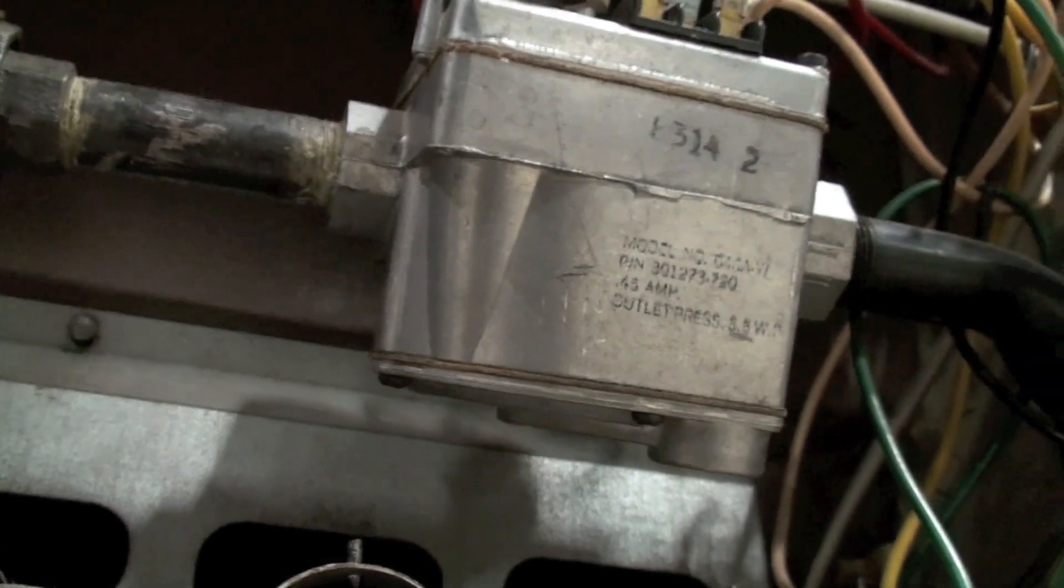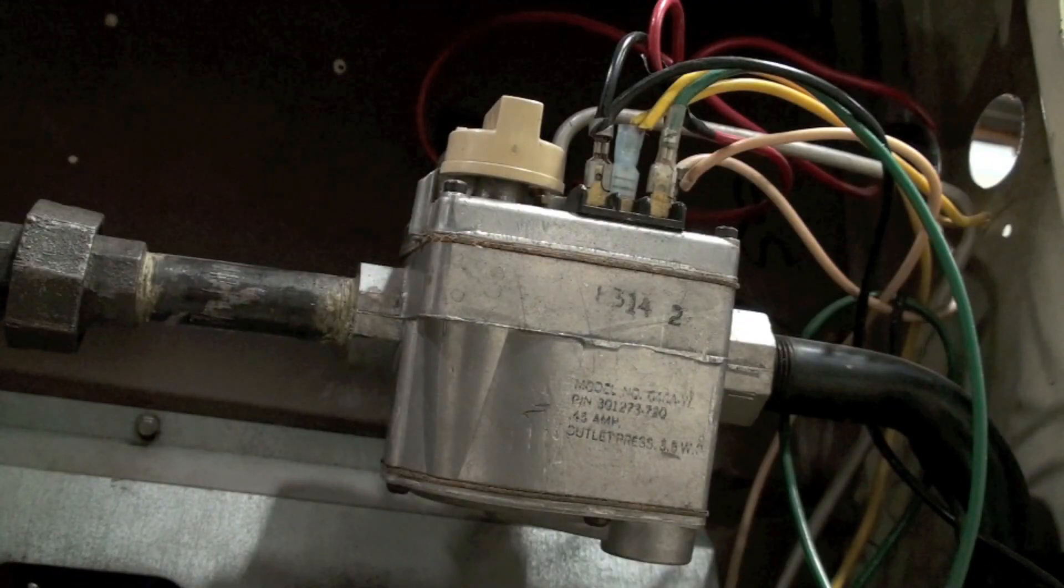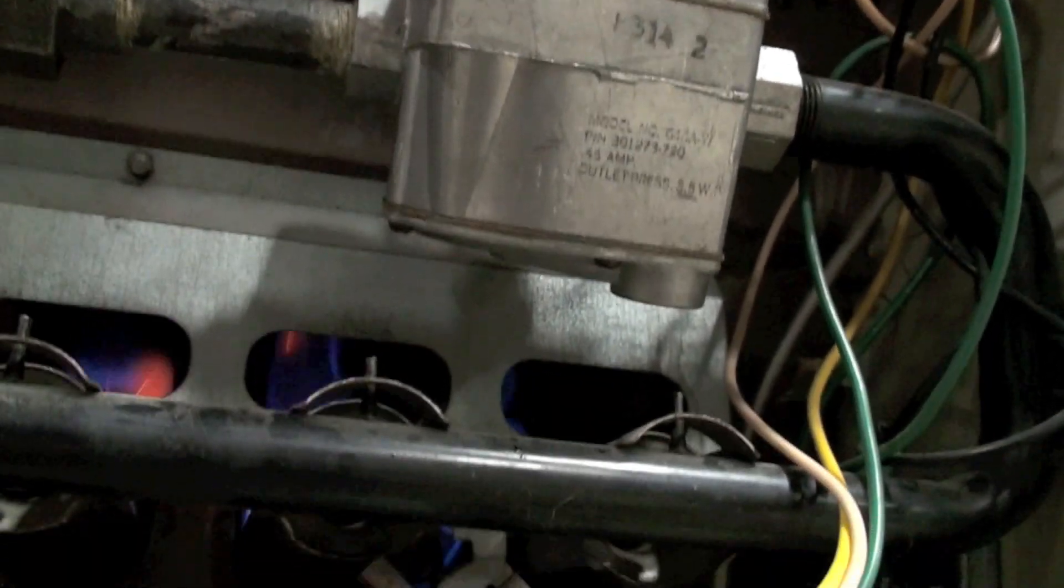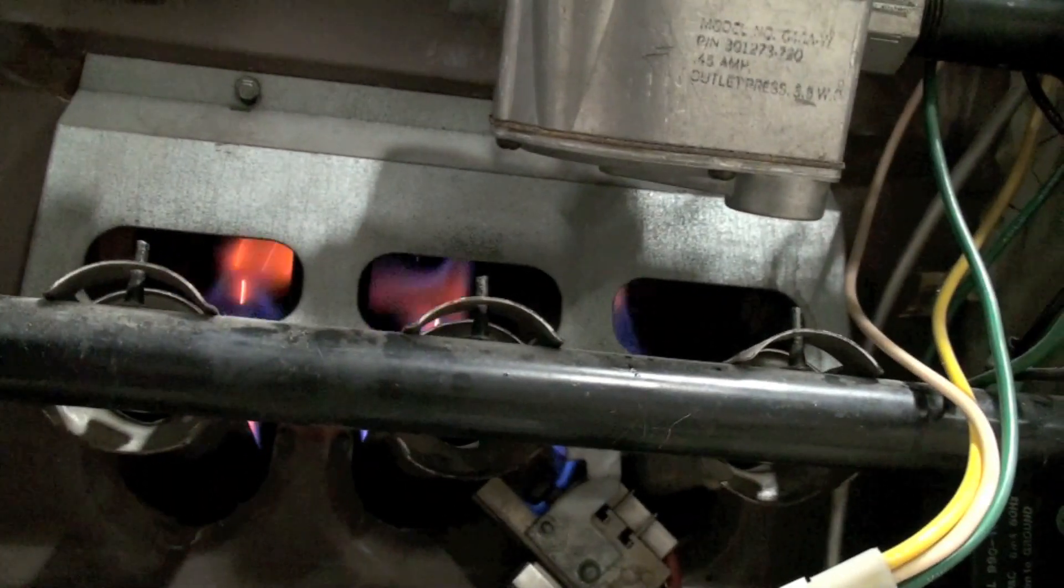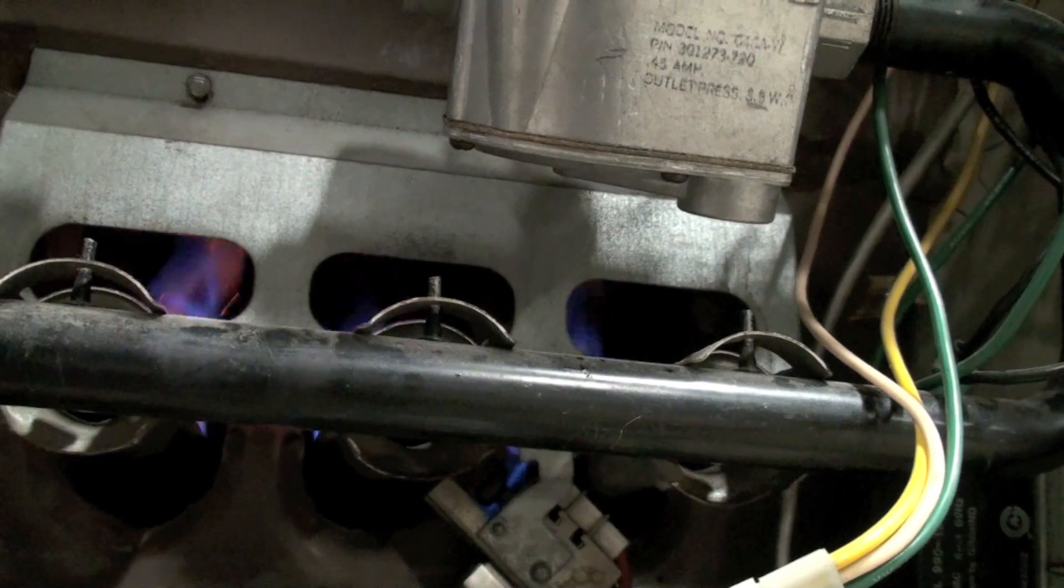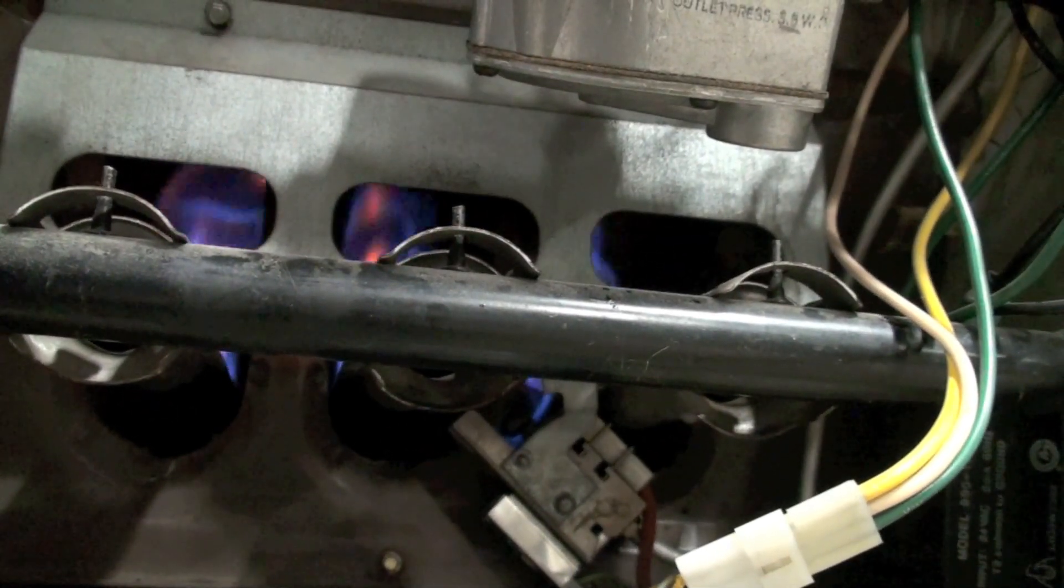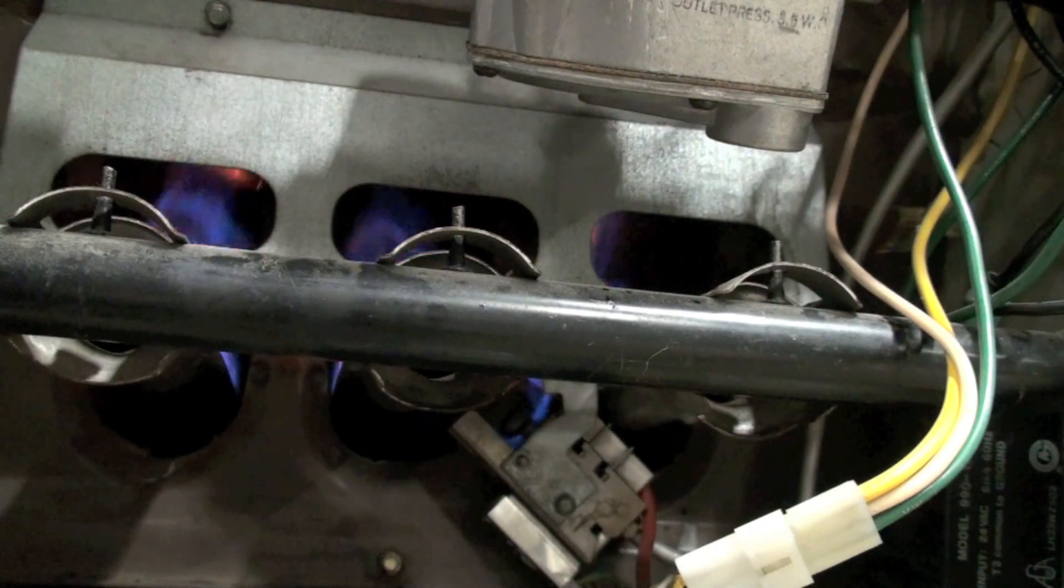Now, that gas valve allows the pilot to come on but won't allow main gas to come on until the pilot has proven—in other words, warmed that bi-metal switch and allowed it to turn over.